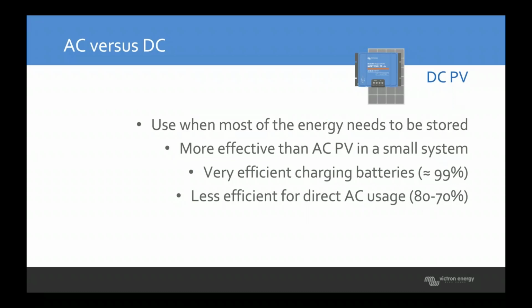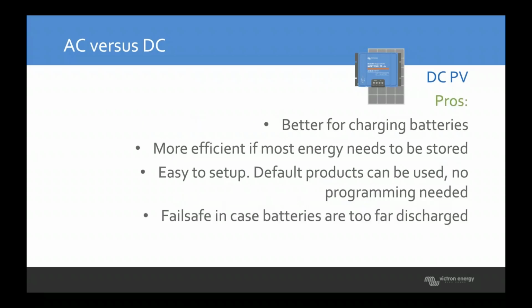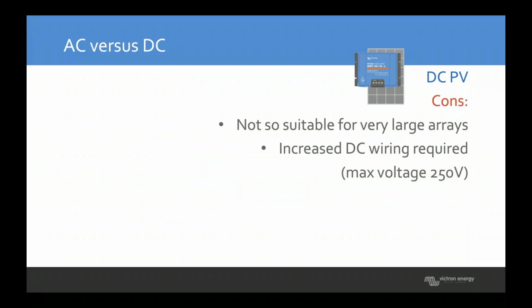They're also extremely efficient at charging batteries. Their conversion is very, very good, but less efficient when running an AC load. So they're better for charging batteries, more efficient if the energy needs to be stored. They're easy to set up, at least in a Victron system, so virtually plug and play. There's a little bit of programming required on the system, but no additional integration programming required. And they can start up a system from a blackstart.